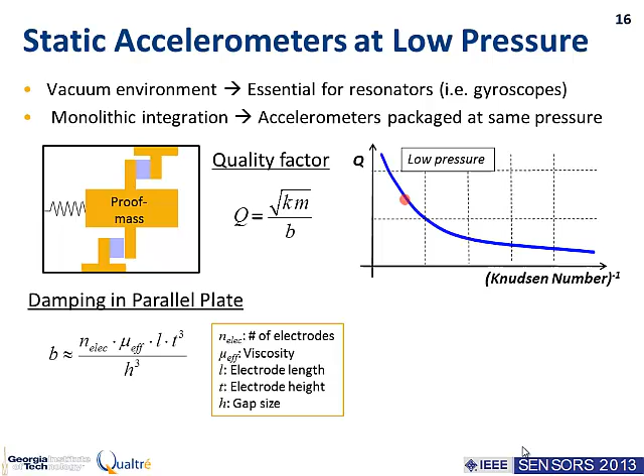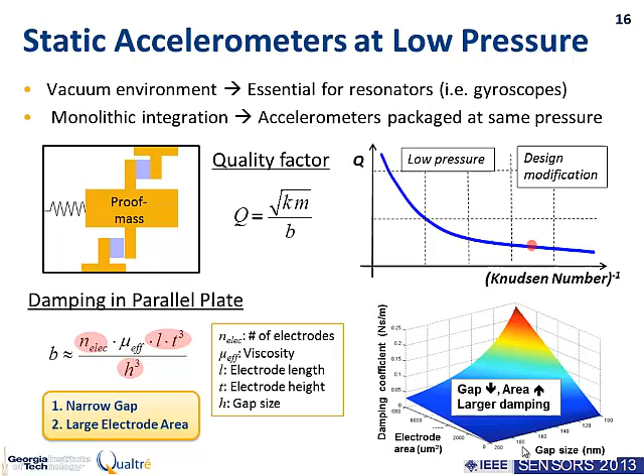to compensate for the decrease in the effective viscosity, like I mentioned before. For example, the gap size or the electrode area. So if we make this very small and add several electrodes, then we can basically bring this damping number back up again, even in a low pressure environment. And an important thing to highlight is that before we do this, we need to see what the effects are of having narrow gaps in capacitive accelerometers.